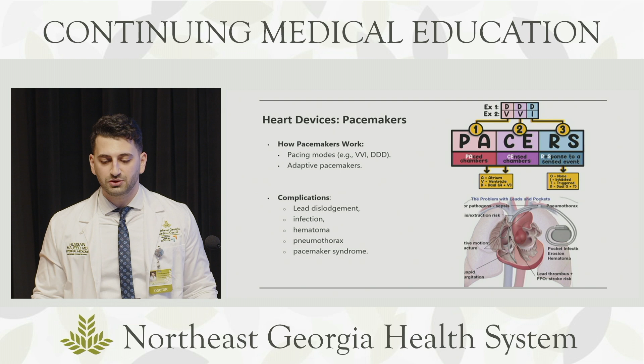These are some of the most common pacing methods. We've got VVI, AAI, and DDD. The first letter represents the chamber that's paced. The second letter is the chamber that's sensed. The third letter is the response to that sensing, whether it's inhibiting or triggering or doing both or doing nothing. And we've got some clinical indications here. I don't want to go over every single one of them, but the most common ones you can see: VVI, the ventricle, also called ventricular demand pacing.